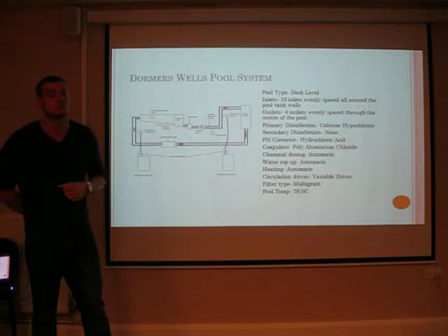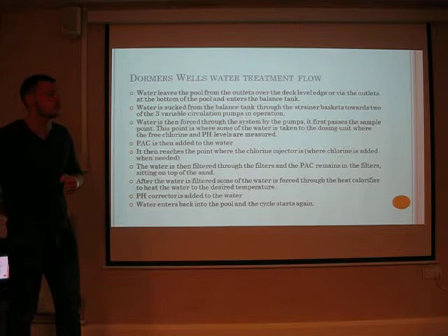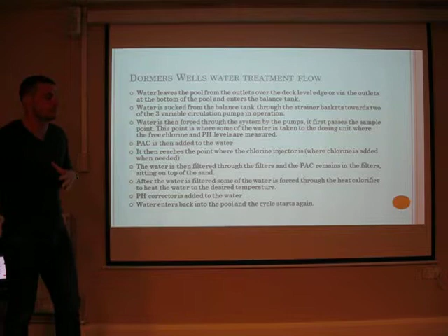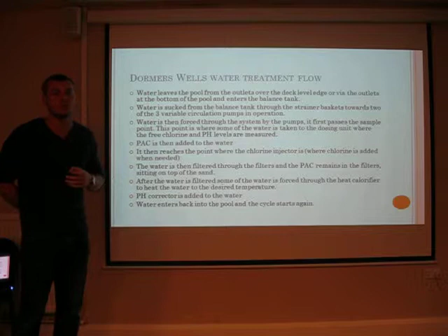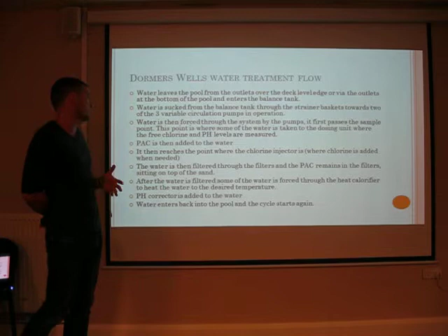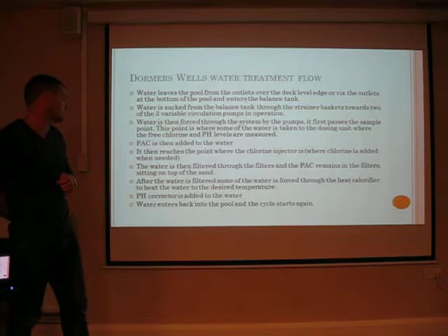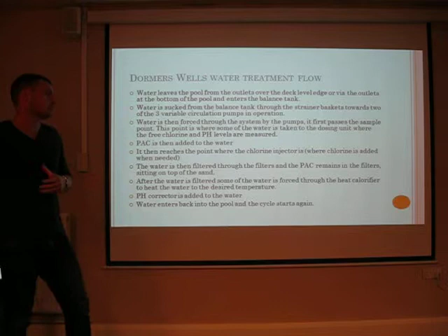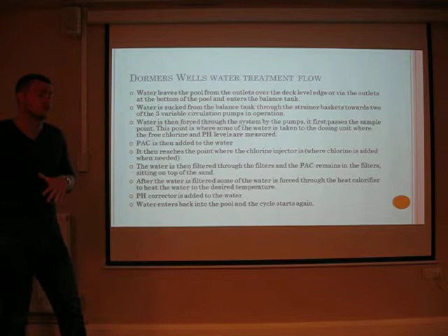The flow of water through the Dormers Wells system: water leaves the pool via the deck level lip or the outlets at the bottom. It's drawn through the balance tank to the circulation pump, passing first through the strainer basket. Pumps force it through the dosing sample point, where free chlorine and pH levels are read. PAC is then added, and chlorine is injected if called for by the dosing unit. Water is filtered, with PAC remaining on top of the first filter layer, then forced through the heat calorifier and heated if needed. The pH corrector is added after this, and the water returns to the pool.